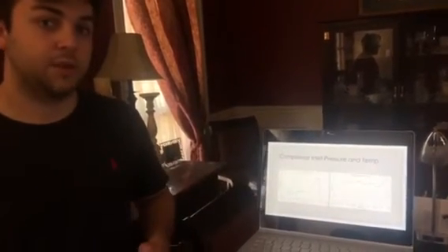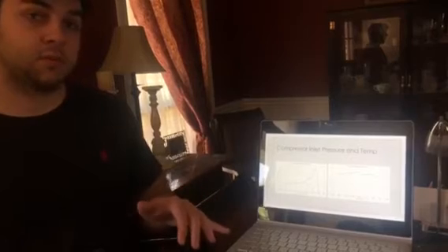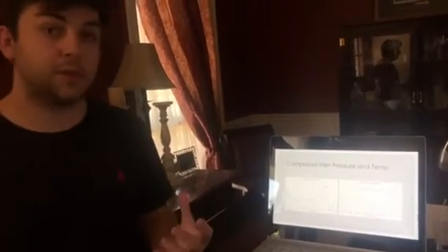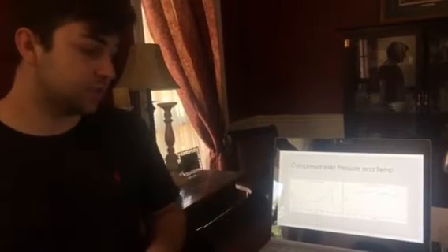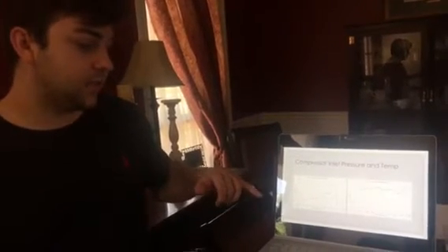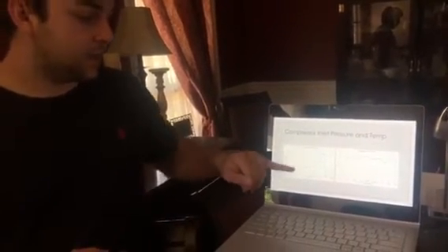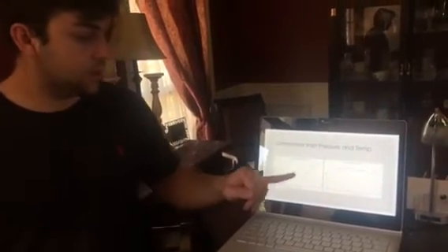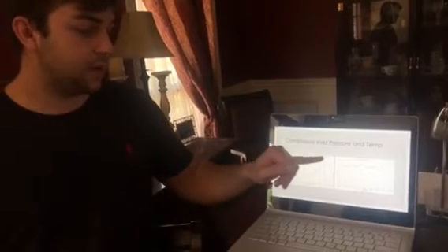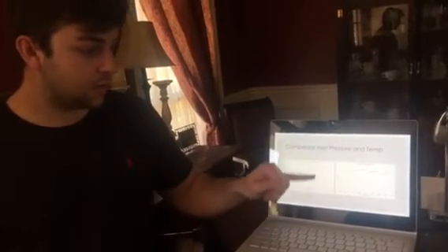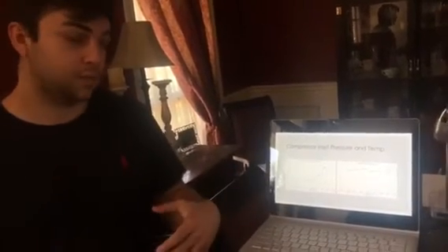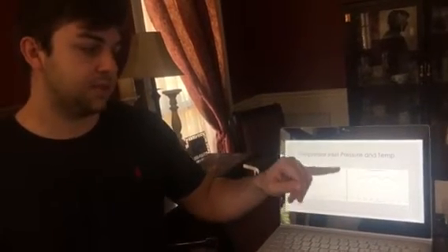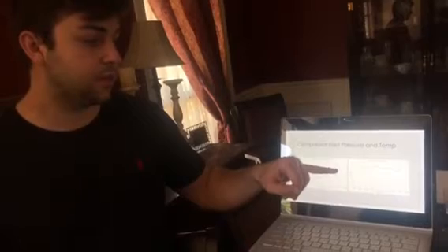The following slide is going to be graphs over time with relation to inlet and outlet values. So on the left, we'll have pressures, and on the right, we'll have temperatures. We can see that there's a very low inlet pressure into the compressor, and then a sharp increase in pressure, followed by a very hard fall off where we end the cycle. And then our inlet temperature fluctuates between about 27 degrees and about 35 degrees.